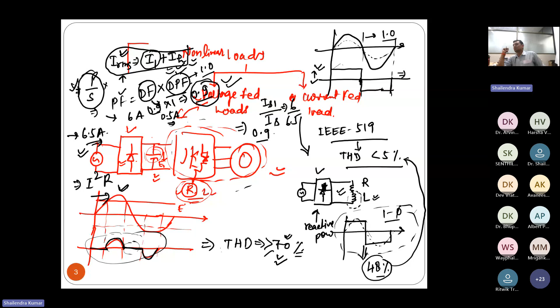If you have a controlled converter, then there will be a reactive power requirement and your power factor may decrease further. And then this converter not only has to address the power quality and power factor correction, it also has to supply some kind of reactive power so that the voltage at the point of common coupling can also be boosted. So this is the second challenge which we have faced and addressed in our systems using intelligent adaptive control to address this power quality issue.